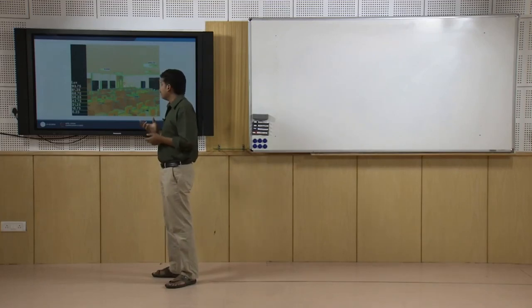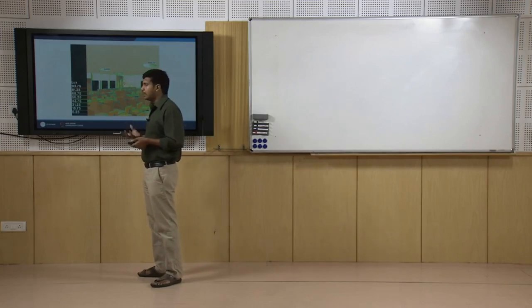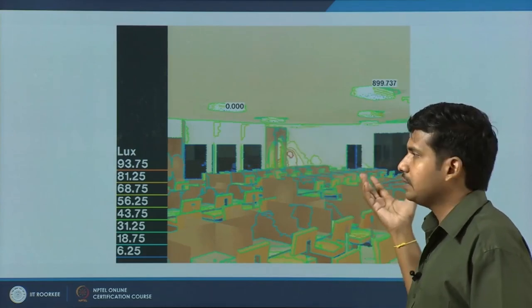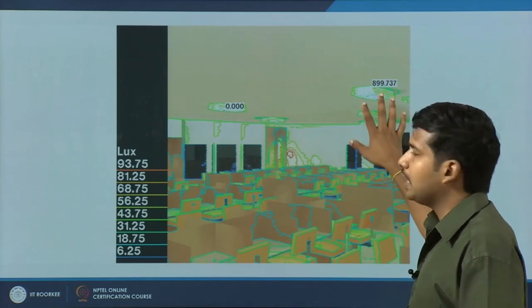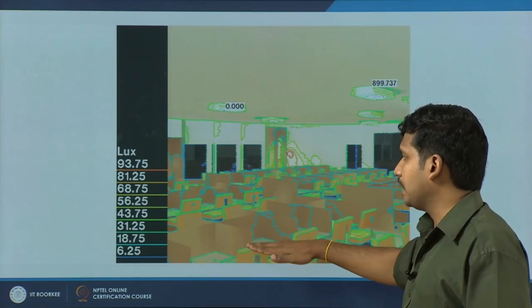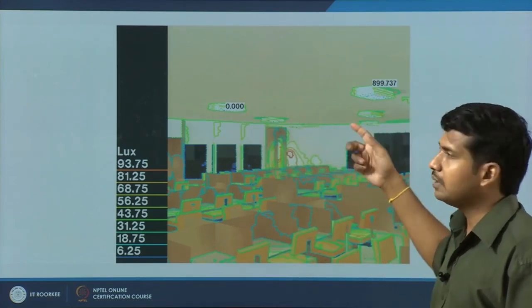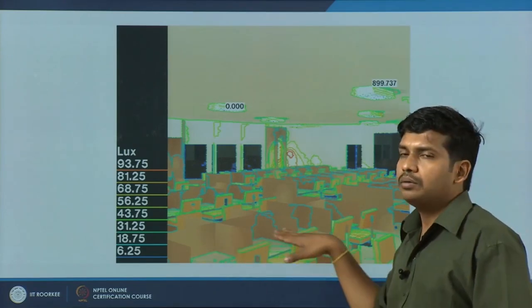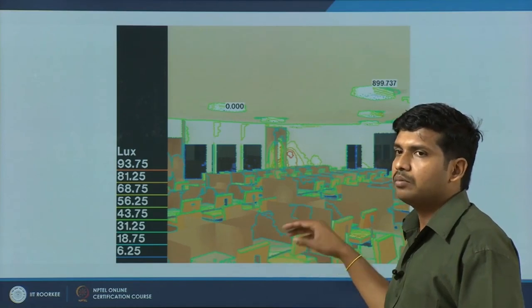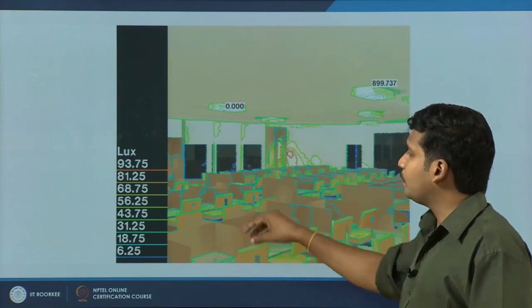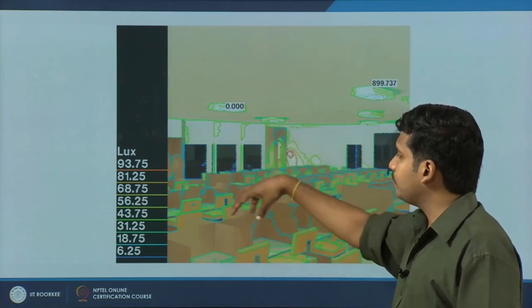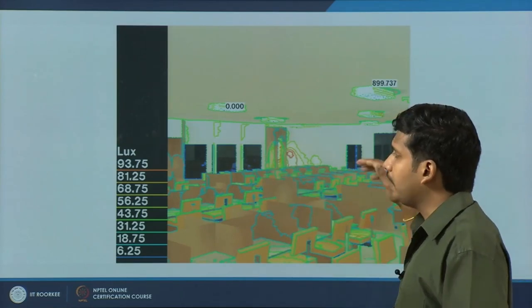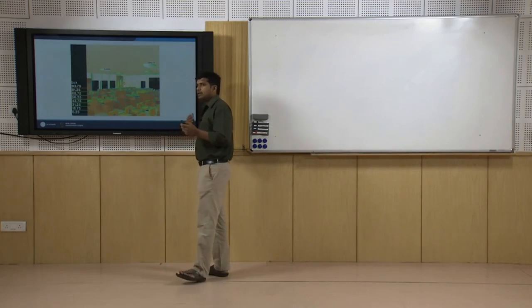You can do a mapping space to space. In a typical open office, if you go with ceiling lights alone and want to ensure 200 lux on the tabletop, you have to increase the number of luminaires. A better, more logical approach is to provide task lighting for individual tables or cubicles. Whenever those occupants are away, the task lights can be turned off, while the background lighting remains at around 100–150 lux to ensure clear visibility of objects.